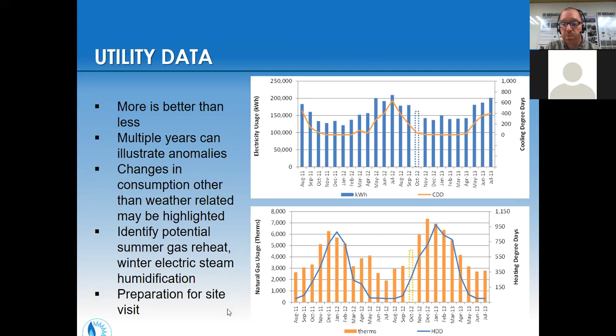On the gas side, notice how much gas is being used during the summer here in the trough between the two winter peaks. And this is excessive reheat. So this is that example where the VAV valves were stuck open and it's having to do a lot of reheat. So the air conditioning is fighting with the reheat, and we're running boiler and chiller at the same time in these cases. Those are some of our first indications to look for before we go on the site visit.